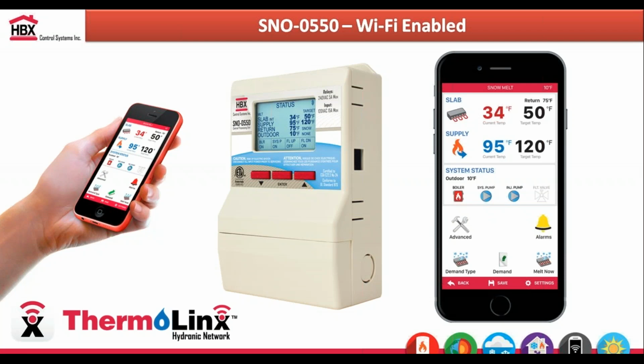So here you can see everything through the HBX app that you would see on the controller, and you can see what devices are on and off. You can also set alarms through this as well. So if your slab temperature were to go below or above a certain target, you'll get an email notification. And the end user has the option to run the system all the time through an idle mode, or if he just wants to go through a cold start, or he has the option of automatically triggering melt now, and he can actually set melt off. So the real nice thing about HBX in terms of the Wi-Fi is that you can see everything, but you can actually change all your system parameters through our app.